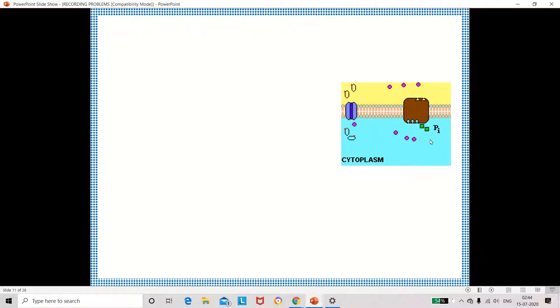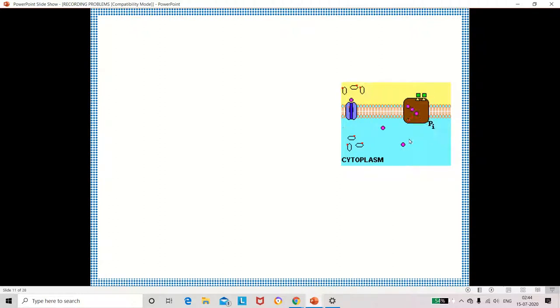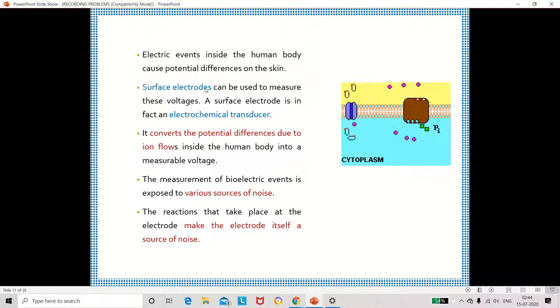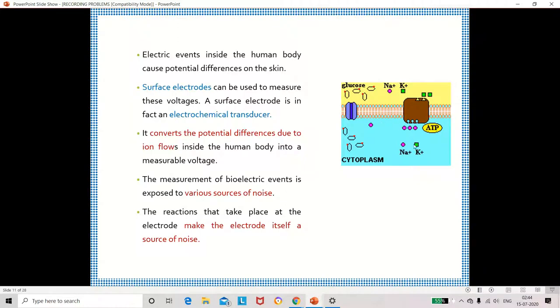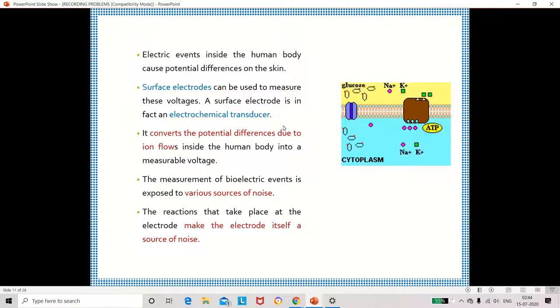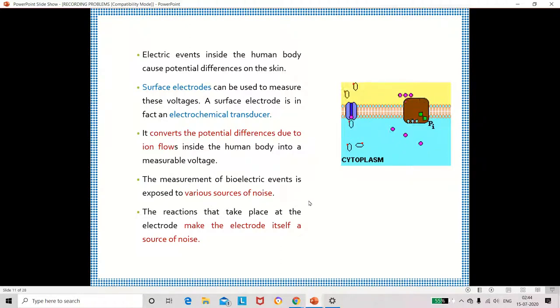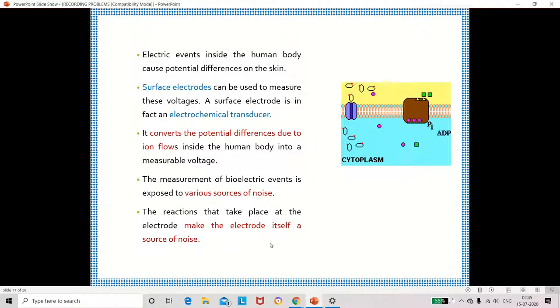The body fluid contains many ions such as sodium ions, potassium ions, and chloride ions. Due to the movement of these ions, the potential is generated from the body. The surface electrode is also called an electrochemical transducer because ionic potentials are converted into electronic potentials. While measuring this potential there is a possibility of noise being added to the signal, as reactions at the electrode make the electrode itself a source of noise.